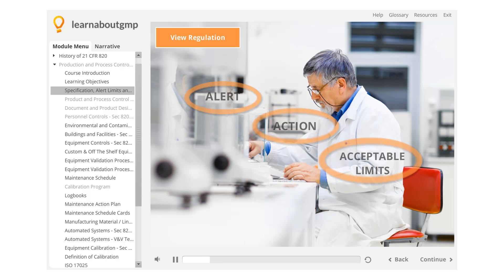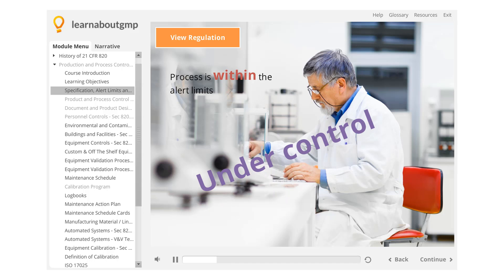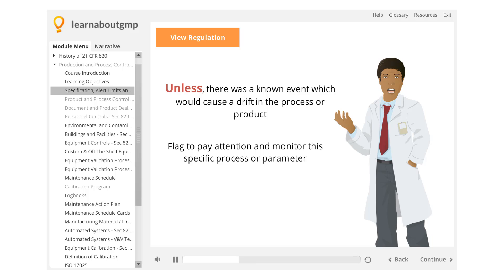As long as the process is within the alert limits, the process or product is said to be under control and will meet its intended requirements. Once a process exceeds the alert limits, this should raise concerns, unless, for example, there was a known event which would cause a drift in the process or product. An action is not necessarily required, but it is a flag to pay attention and monitor this specific process or parameter.